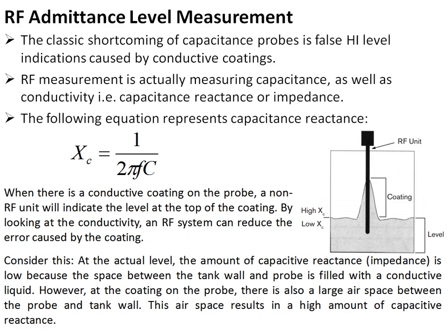To eliminate the coating-error problem, RF admittance level measurement is used. In addition to measuring capacitance, it also measures conductivity — which is inversely proportional to capacitive reactance or impedance, given by 1/(2π·f·C), where f is the operating frequency of the level sensor. A normal capacitance-based unit will indicate the level at the top of the coating because the coating increases capacitance, producing an erroneous reading. RF admittance measures impedance in addition to capacitance.